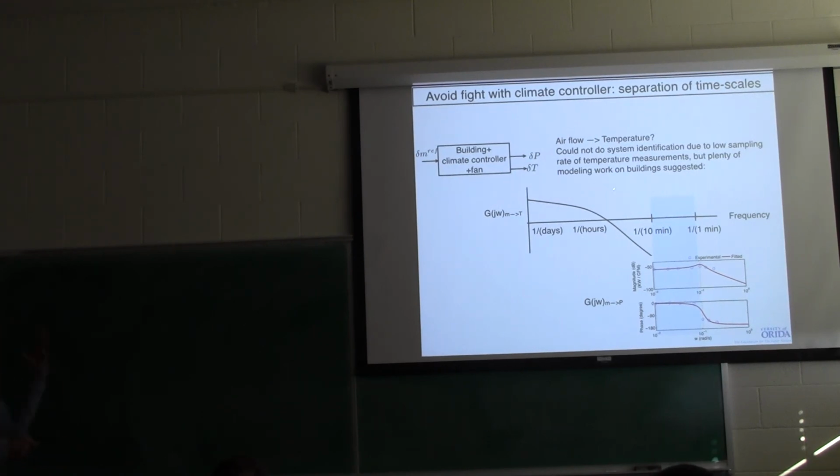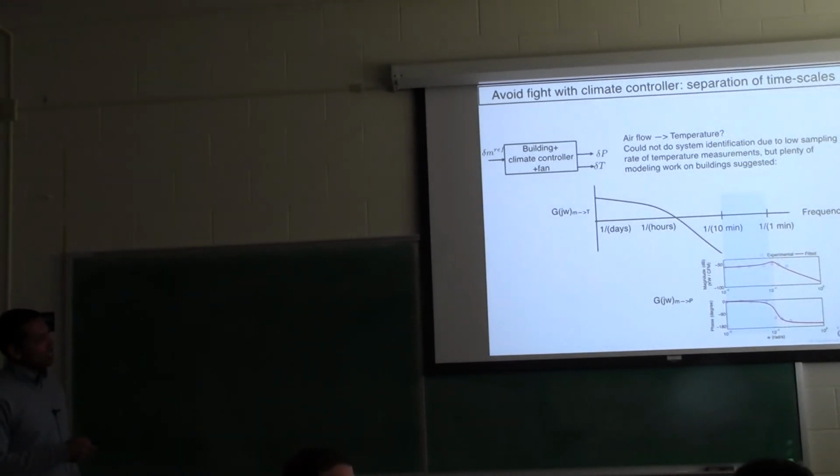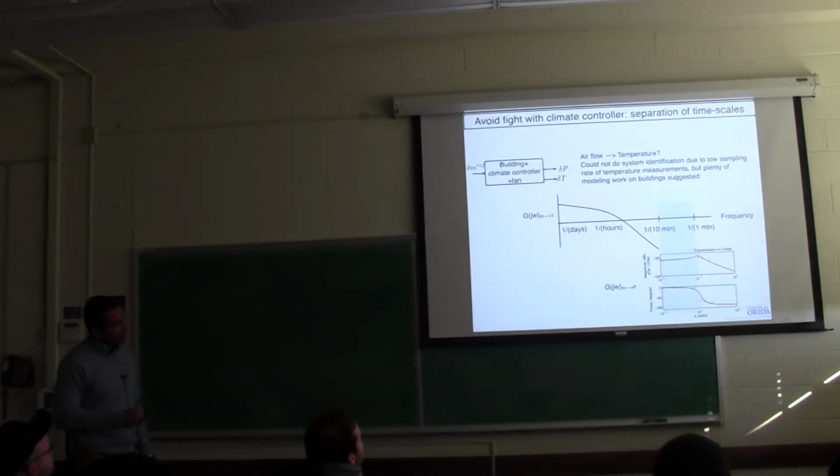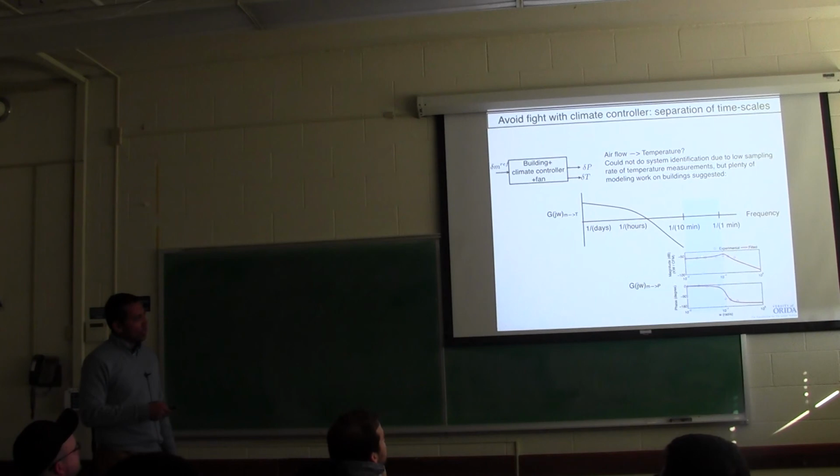We don't have experimental data for how this affects the temperature, because the temperature measurements are really slow. But we did a lot of modeling work to convince ourselves that in this range of frequency, where the power consumption reacts quite fast to airflow rate, temperature doesn't react at all. So it's like, okay, this is the range.